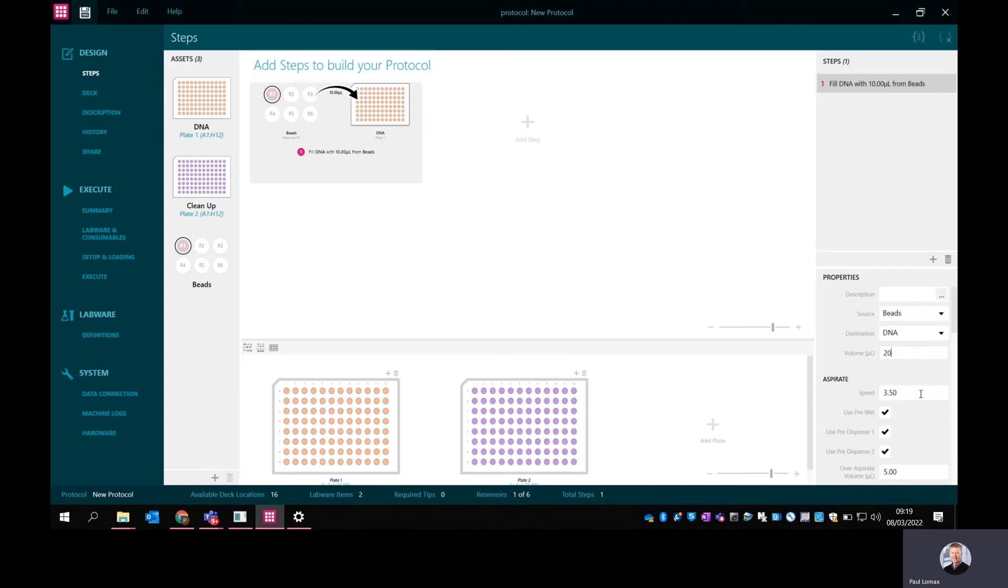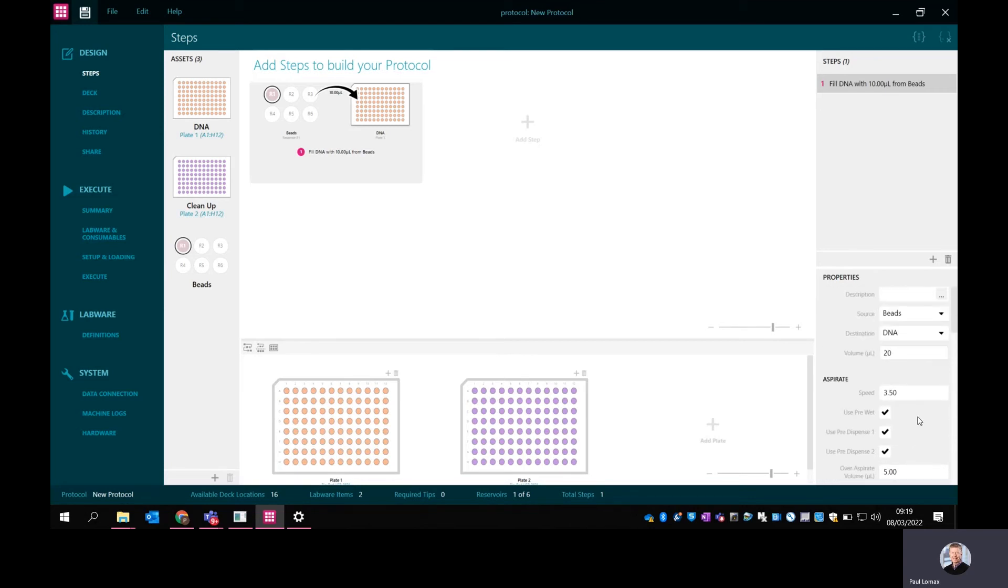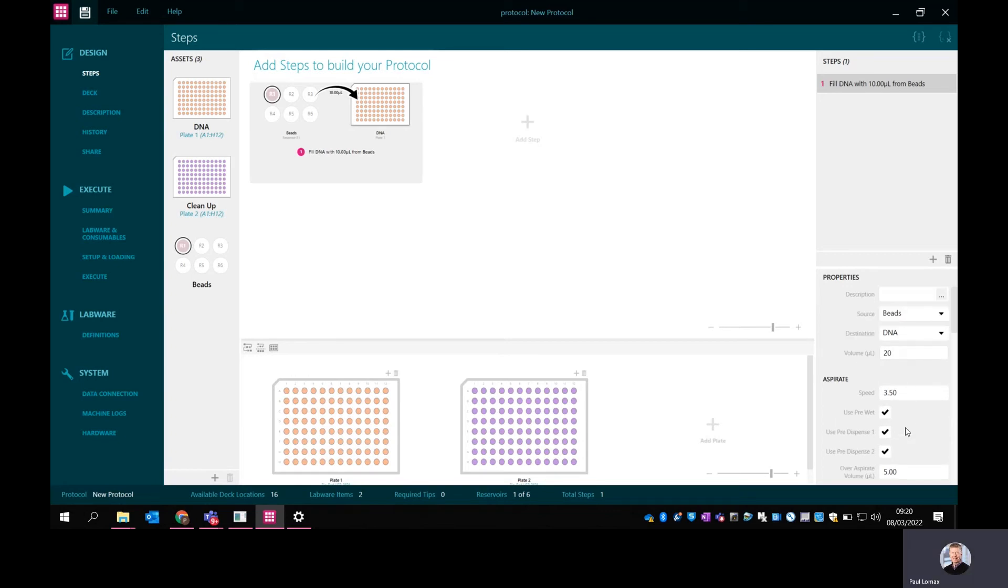The rest of the parameters as I scroll down here are the more advanced settings in terms of speeds, aspiration speeds, pre-aspirate volumes and so on. These are defaults in the dispenser and you can use this straight away without having to change any of these standard settings. This is using the positive displacement non-contact dispenser, which is very adaptable to work with different liquid types without needing to change any of the settings. However, the settings are there and available if people want to fine tune them. I'm just going to leave that at 20 microliters.